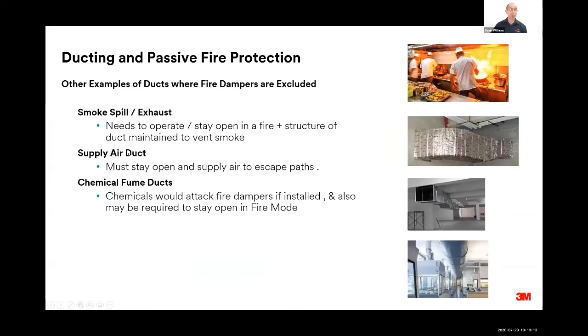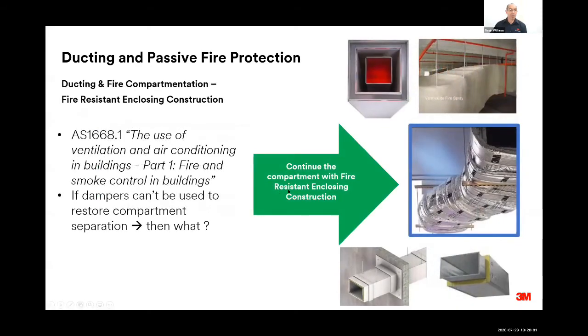Other ducts that usually don't use fire dampers are smoke spill and exhaust ducts. Again, they need to operate or stay open in a fire, and also the structure of that duct needs to be maintained during a fire in order to adequately vent smoke from the building. Also supply air ducts may need to stay open to supply fresh air to escape routes, stairwells and the like. And also chemical fume ducts, for example in laboratories and hospitals, where there may be chemicals in the exhaust gases that could damage fire dampers if they were installed. And again, they may also need to stay open in fire mode in some cases. So we have instances where we can't use fire dampers, and the Australian standard AS 1668 describes where fire dampers shouldn't be used, and also describes what the alternative is.